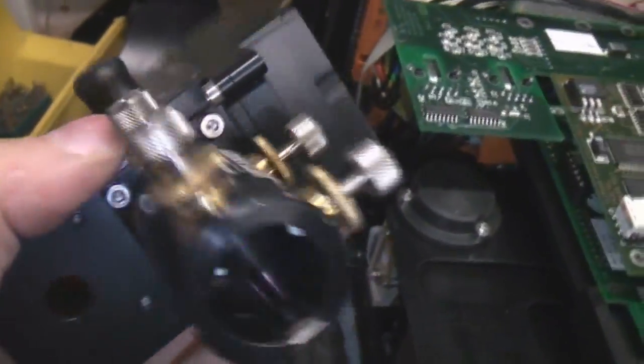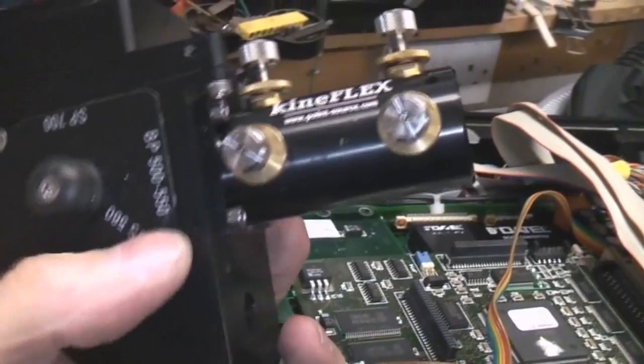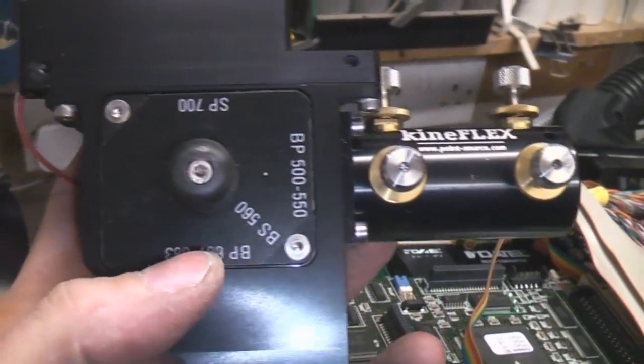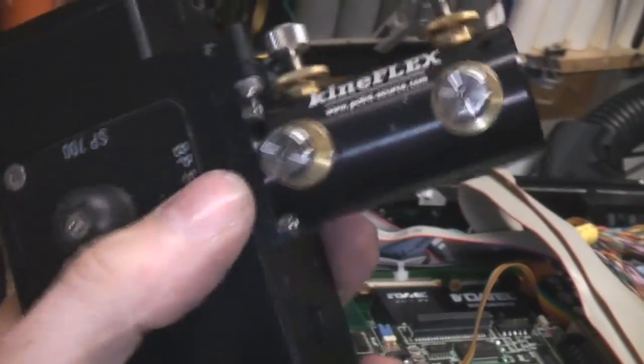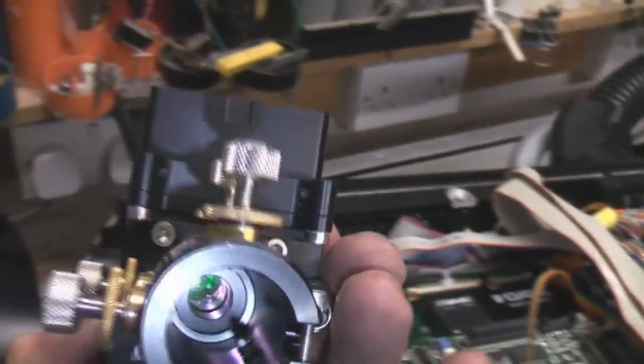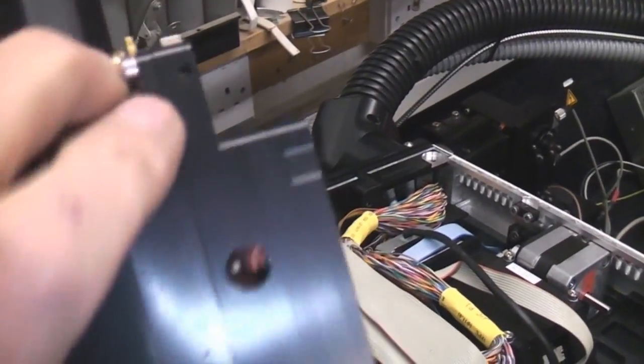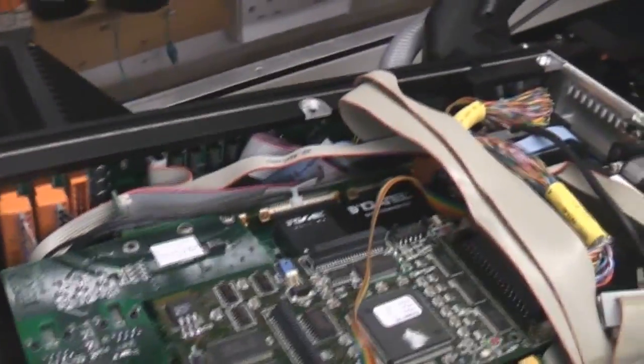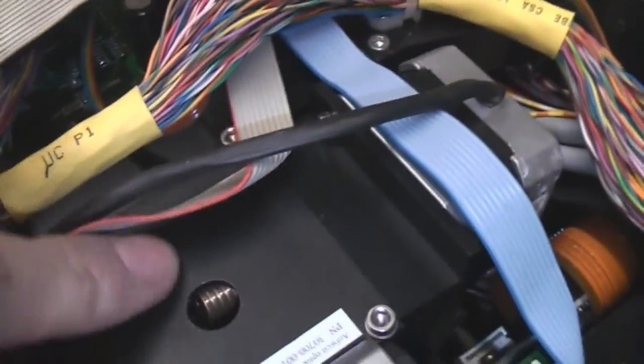got another fibre optic coupling on it, so that's, again, whether that's from another laser or something, I don't know. There's some labelling on here which is a BP 500 to 550, 560, 607 to 683, so that's going to be some sort of beam splitter or wavelength filter or something, because there's quite a few. There's sort of an opening there, one there, another one on this side, and another one there. So again, whether that's the output or some inputs from another laser or something, I don't know. But that clearly was originally screwed into there, but that's come off at some point. Actually, I can just see a bit of flex cable on there, so there's probably another rotating assembly in there, but I can't actually get at the motor.